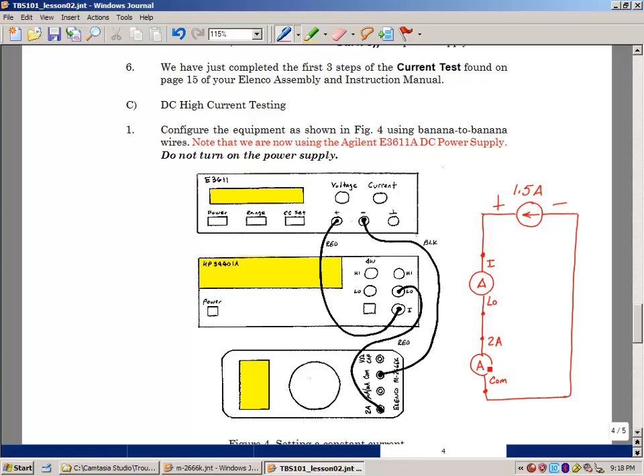Notice in some of these connections with wires, I've labeled some wires as red and black. I tend to put things out of the plus terminal with a red wire and then on the minus terminal with a black wire. That doesn't really make any difference when you hook these things up, but when you're trying to troubleshoot something, if things are color-coded, it makes it a little bit easier to follow what's going on, or if you've done something in the past and come back to it, it's a quick way to be able to identify what's going on.